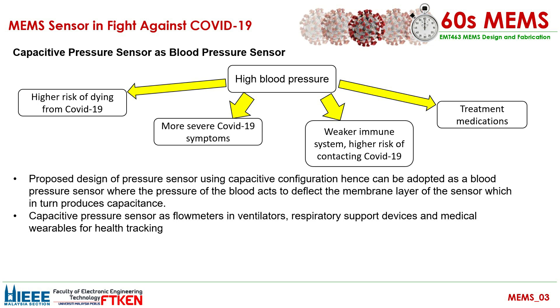Therefore, the proposed design of a pressure sensor using a capacitive configuration can be adopted as a blood pressure sensor, whereby the pressure of the blood deflects the membrane layer of the sensor, which in turn produces a capacitance reading. The capacitive pressure sensor can also act as a flow meter in ventilators, respiratory support devices, and medical wearables for health tracking. That's all from us — thank you for watching.